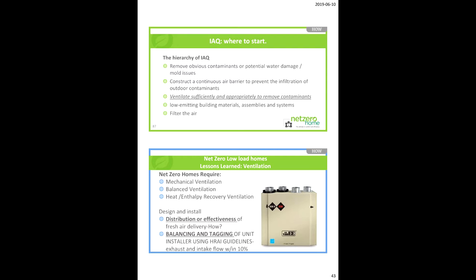It's geometry that makes the difference, not the CFM. The other part is that it doesn't get enough air, but we'll get there. Ventilation doesn't provide combustion air. If you're using gas appliances, your HRV or ERV isn't going to provide fresh air to overcome that. That's a different story.